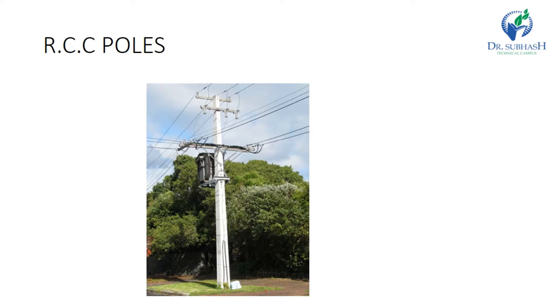RCC pole — a reinforced concrete pole — has become very popular as a line support in recent years because they have greater mechanical strength, longer life, and permit longer spans than steel poles. They give good outlook, require little maintenance, and have good insulating properties. RCC poles are available for both single circuit and double circuit configurations. Holes in the poles facilitate climbing and at the same time reduce the weight of the line support. The main difficulty with the use of these poles is the high cost of transport, so such poles are often manufactured at the site to avoid heavy transportation costs.